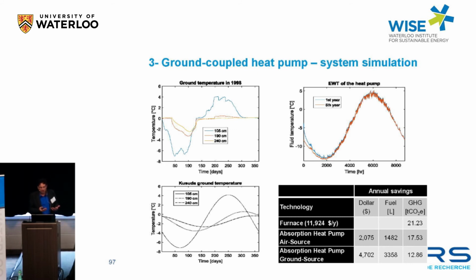You have a working fluid below minus 10 degrees. It has to be antifreeze to work, of course, but you can still decrease its temperature and have a low COP, coefficient of performance, for absorption heat pumps. That could be a COP of 1.2, 1.5, let's say. And we compare these scenarios for heating the building with the conventional fossil fuel furnace. That would cost over a year roughly $12,000.